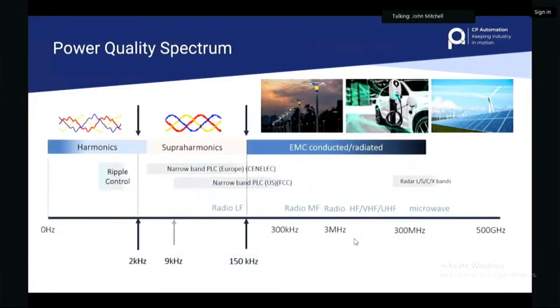So here we're just going to talk about the spectrum now, just so you understand what we're talking about when we talk about noise, right? Forgive me if people don't know, but on the left-hand side, we have harmonics. That's from 50 hertz to 2 kilohertz. That's how it's defined in the standards pretty much globally. Then we have a bit of an overlap. We have supraharmonics, and that's starting at 2 kilohertz and going to 9, and then from 9 to 150.